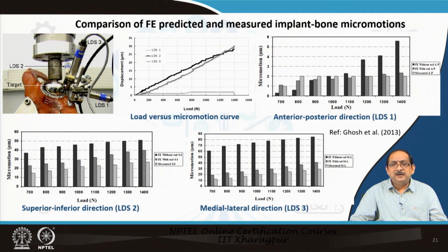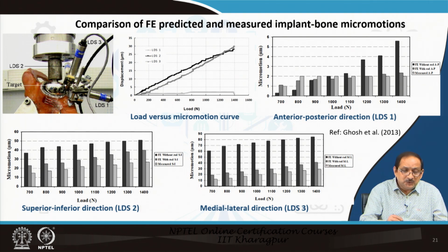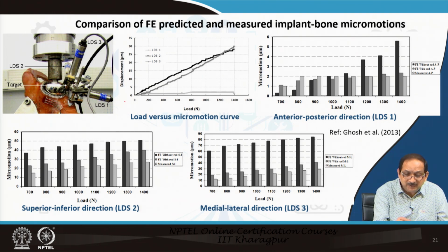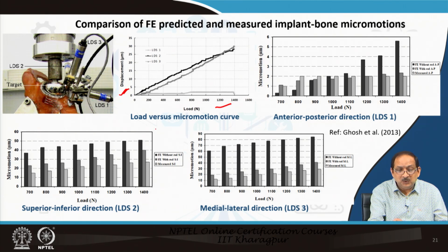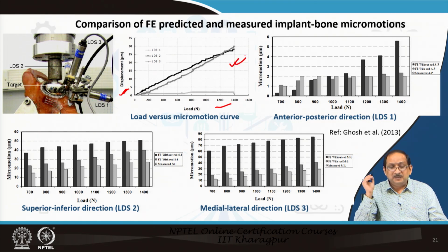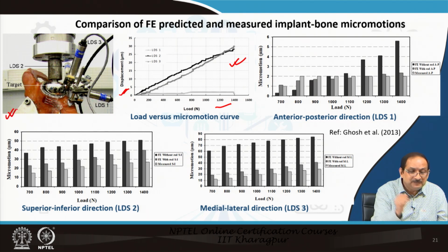Let us now compare the FE predicted and measured implant bone micromotion. We have measured the micromotions or displacements against load, and the load versus micromotion curve is presented here in the slide, based on the experiment performed here.